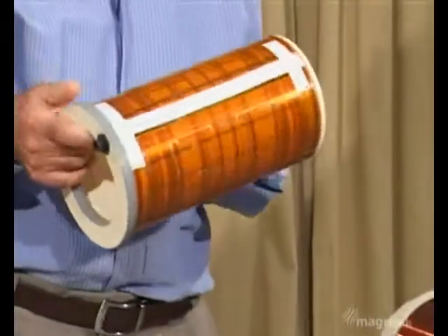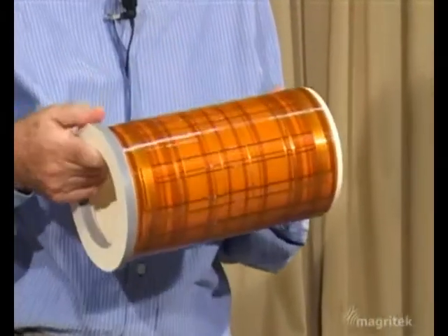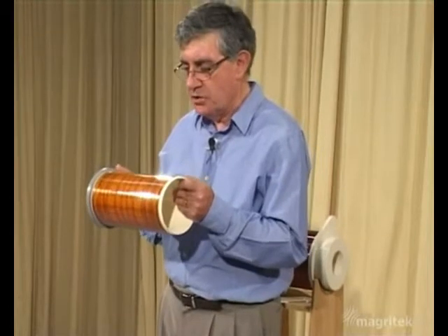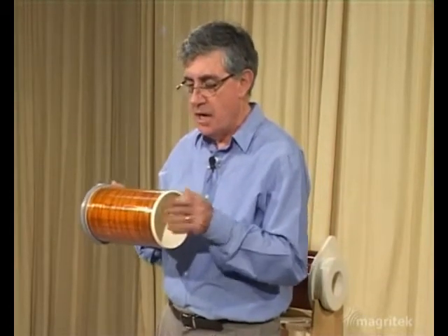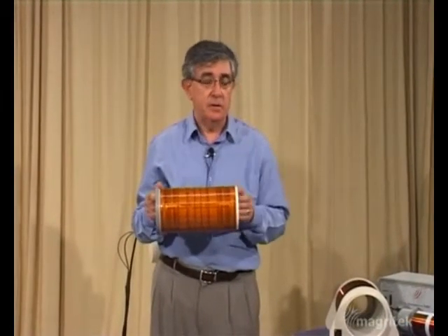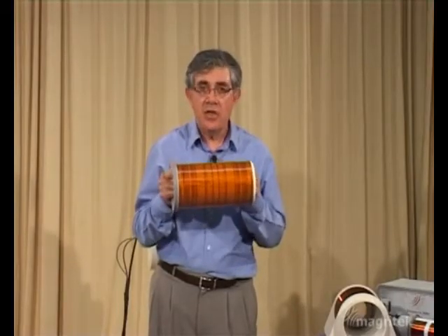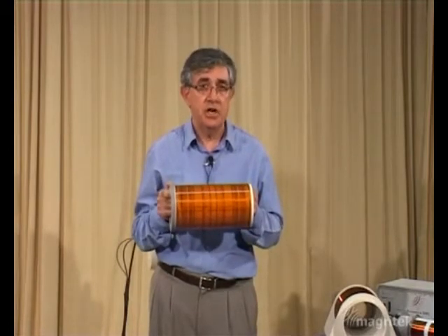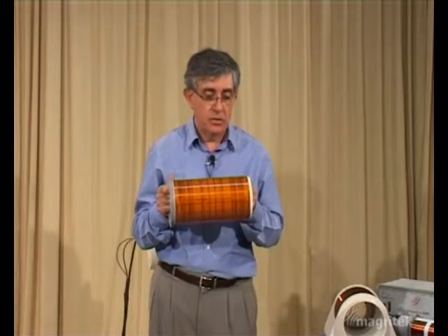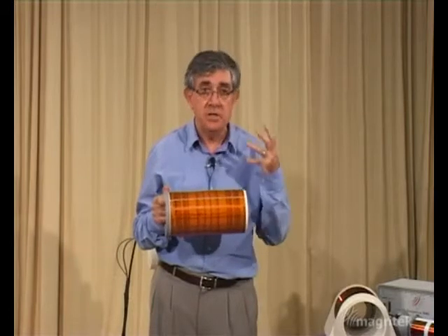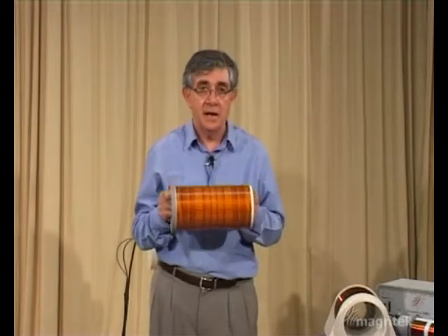This is a very complicated looking coil. It's got lots of layers and it's got some very ingenious patterns in the windings. What this coil does is to produce a magnetic field that varies in 3 orthogonal directions. And these varying fields are known as magnetic field gradients. The use of these coils is that they lie at the heart of magnetic resonance imaging. By varying the magnetic field in 3 orthogonal directions, we can produce a Larmor frequency that depends upon position. And that's the basic principle behind MRI. We'll be looking at that in a later video.